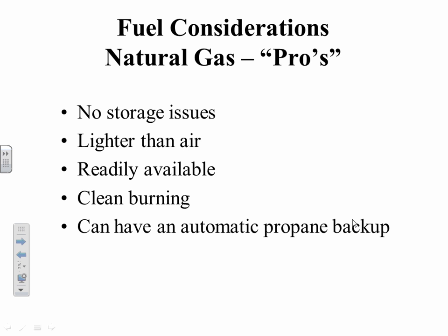All right, fuel types. The main thing we'll talk about right now is natural gas. These again are in smaller sets, and I do have a few opinions that I'll share with you as we go through. But on the pro side of why we would use natural gas is there are no storage issues. We don't have to worry about filling a tank. We don't have any of that. It's lighter than air, so if there's ever a leak, it's going to go up, not down. Natural gas is readily available. It is very clean burning as opposed to the other fuels, and it can also have an automatic propane backup.